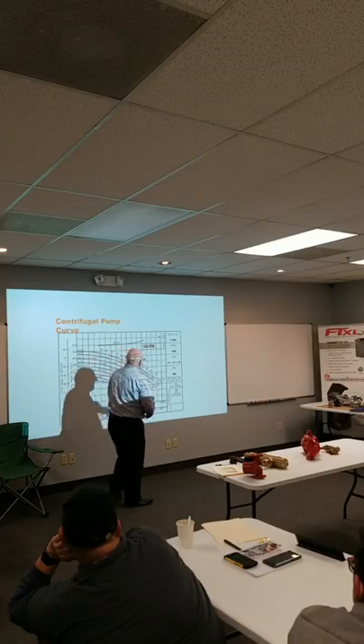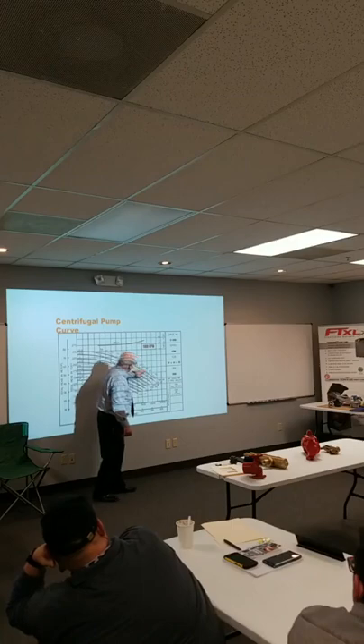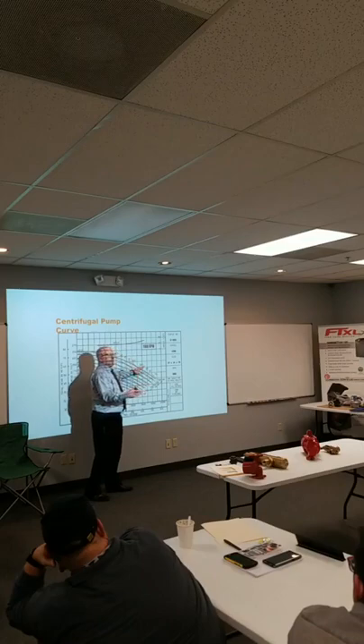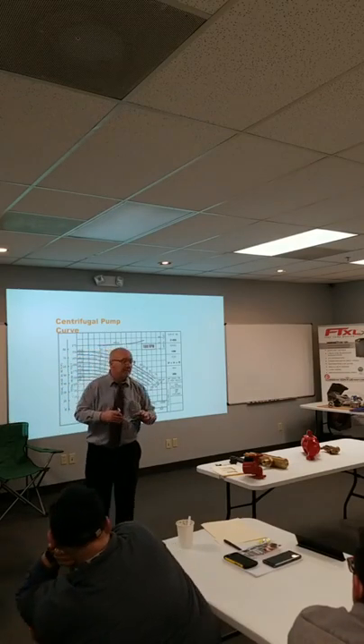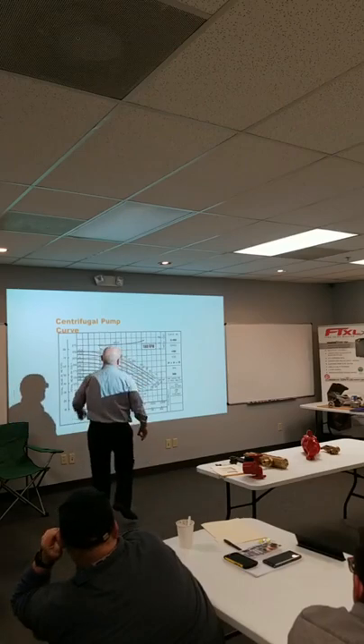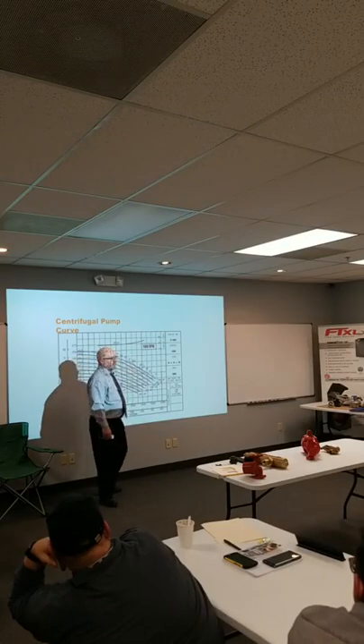And when I talked about throttling back a pump, if a pump's running out on the curve, and these are the horsepower lines, and it was designed here, but there's less resistance in the system, and it's running out here, you're overloading the horsepower. Your amps are going way up. What you have to do is throttle it back, and that's why the discharge valve on a lot of pumps are throttled. Oh, you mean it's like over FLA or something? Yeah, like that. Or just knocking out the breakers completely. I've seen it. Wow. So they balance it, they bring that pump back on the sweet spot of the curve, which is in the middle of the curve.